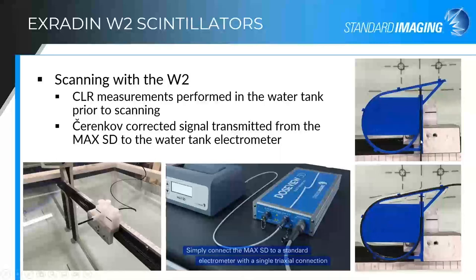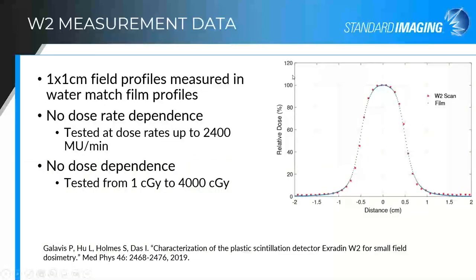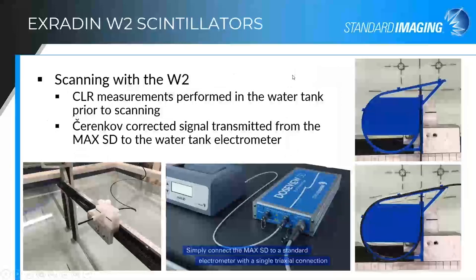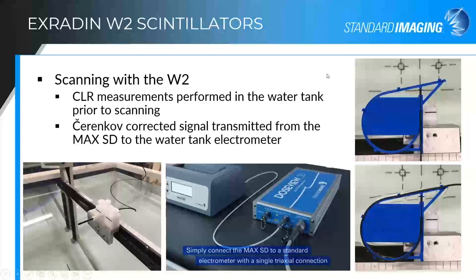This shows the minimum versus maximum fiber configuration in the water tank. You don't need to perform this every time you scan — it's a one-time setup prior to scanning and then occasionally afterwards. The signal from the scintillator tends to decrease by about 2% for every thousand gray received, so it does require periodic recalibration throughout its lifetime.